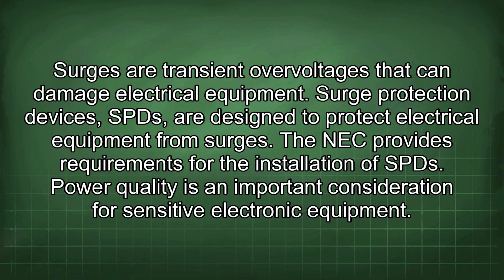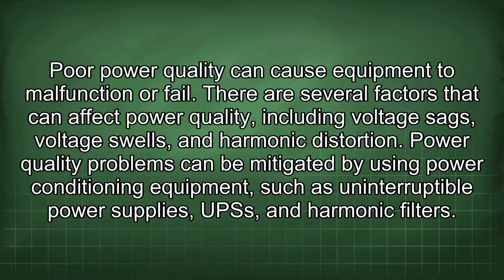Power quality is an important consideration for sensitive electronic equipment. Poor power quality can cause equipment to malfunction or fail. There are several factors that can affect power quality, including voltage sags, voltage swells, and harmonic distortion. Power quality problems can be mitigated by using power conditioning equipment, such as uninterruptible power supplies, UPSs, and harmonic filters.